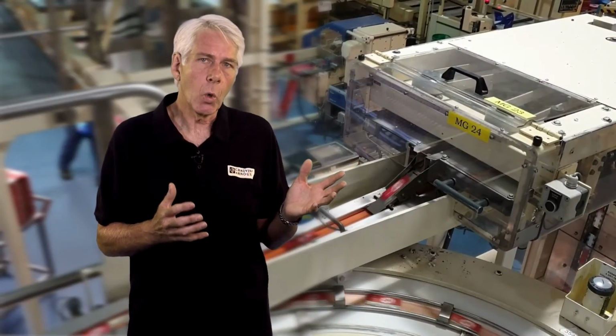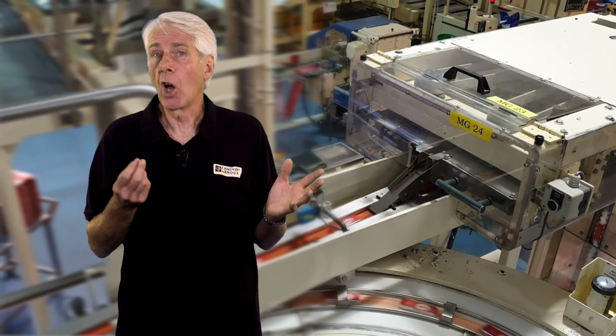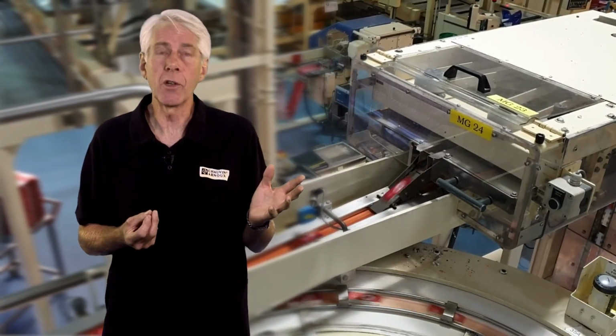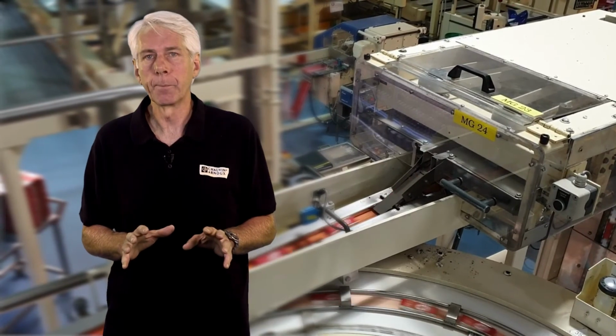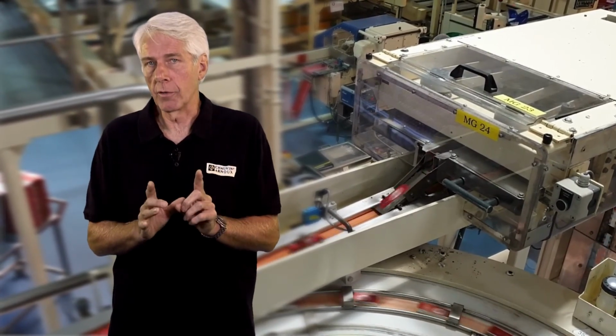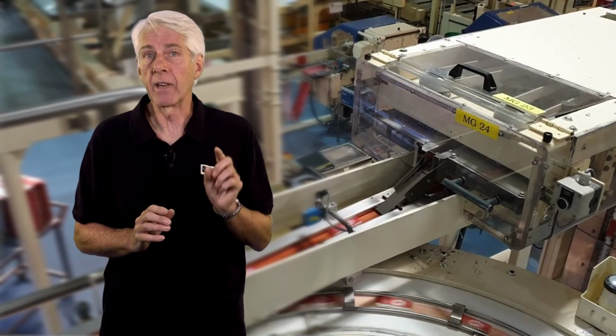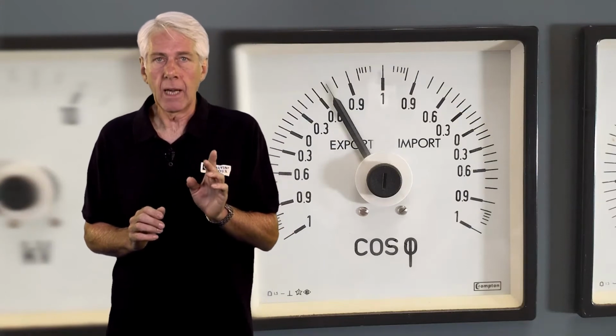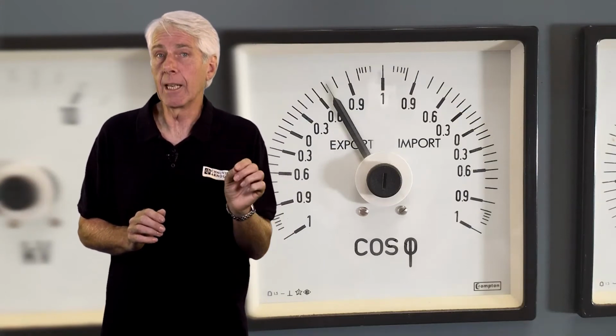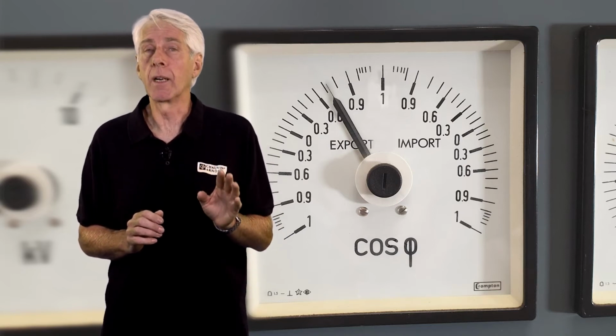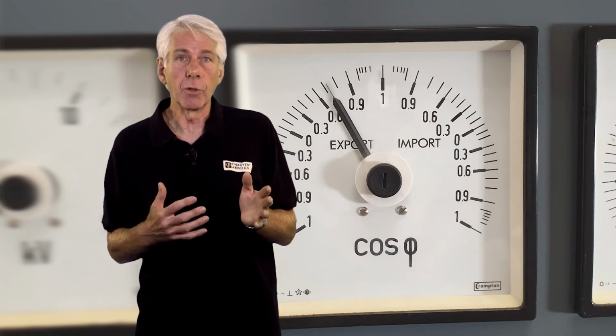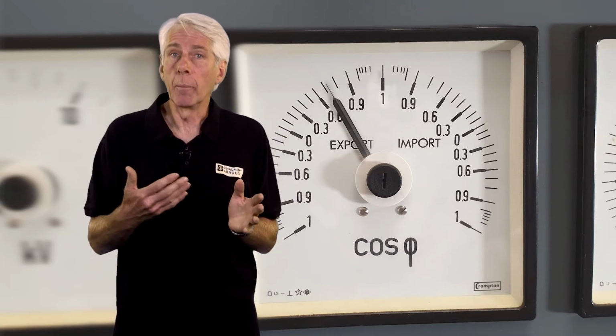With modern equipment, it's not quite as simple as that, due to the need to consider harmonics and other power quality issues caused by non-linear loads, and we'll touch on these later. Either way, there are two common issues that result in 50% of UK industries having inadequate power factor correction today. Firstly, PFC equipment calculated to suit the loads in a business at a point in time may no longer be appropriate as time passes. This is mostly due to new equipment being added and old equipment being decommissioned. And secondly, and perhaps more significantly, the capacitors in power factor correction equipment wear out over time.